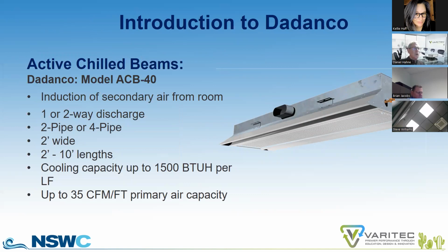Active chill beams, the conventional workhorse that we see over and over again because of its price point and its capacity, is Dadanco's ACB-40 model. This is the device that was illustrated in the configurations I provided earlier. These devices can come in 24-inch wide or 12-inch wide configurations with 1-way or 2-way throw. They can be 2-pipe or 4-pipe configurations. Then the chill beam application for the Banner Health University Medical Center in Tucson, AEI was the engineer. And I'm finding this in healthcare for tighter control. They're opting for 4-pipe configuration.